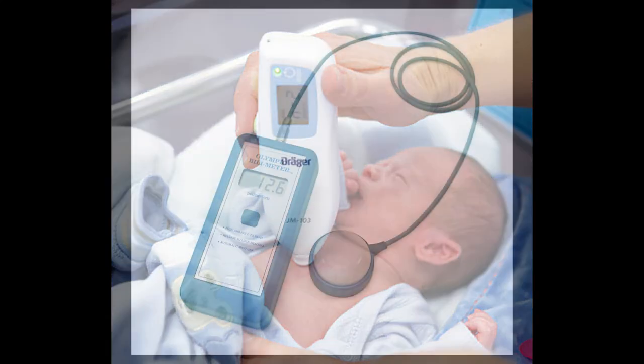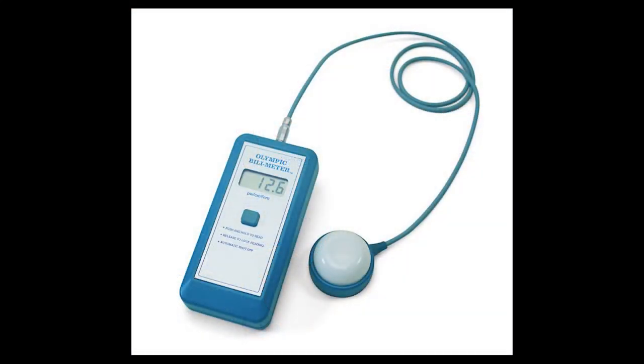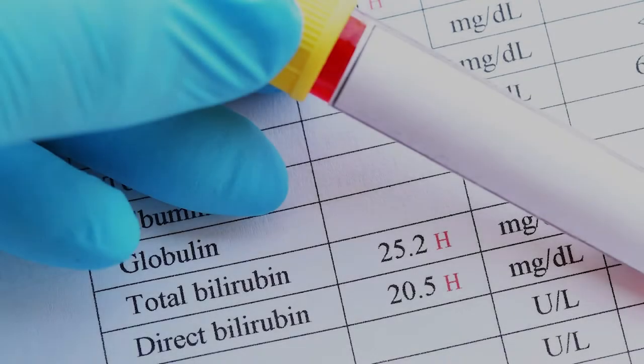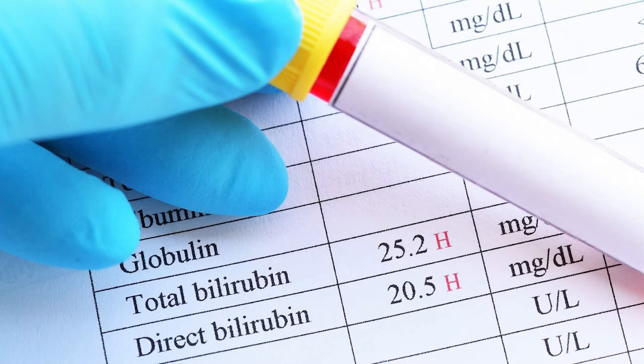Bilirubin levels are checked by either skin or blood tests. Skin checks are performed with a bilimeter — a light meter which sends out white light into the skin and measures the intensity of certain wavelengths of reflected light. The measured amount of reflected light is proportionate to the amount of bilirubin in the bloodstream.